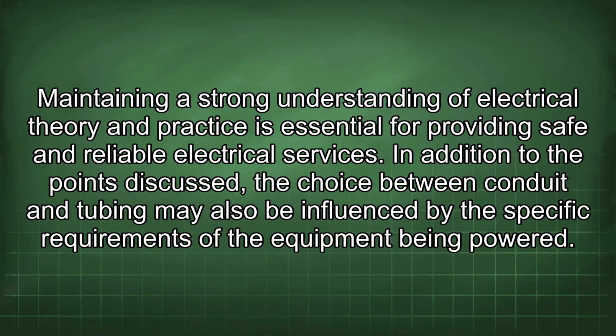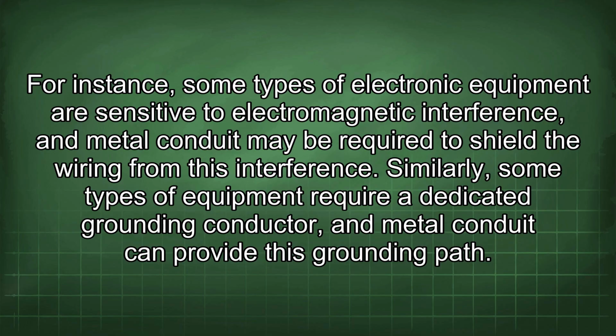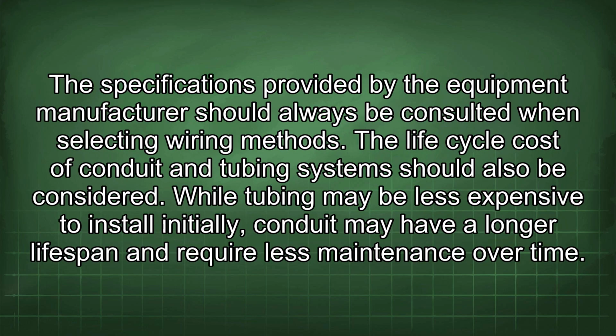In addition to the points discussed, the choice between conduit and tubing may also be influenced by the specific requirements of the equipment being powered. For instance, some types of electronic equipment are sensitive to electromagnetic interference, and metal conduit may be required to shield the wiring from this interference. Similarly, some types of equipment require a dedicated grounding conductor, and metal conduit can provide this grounding path. The specifications provided by the equipment manufacturer should always be consulted when selecting a wiring method.